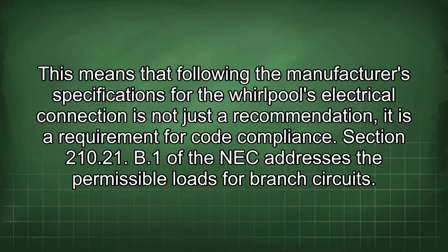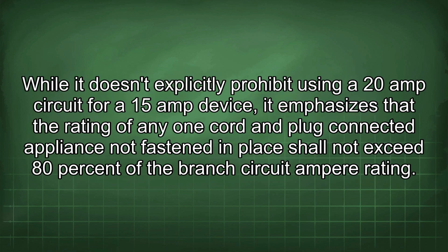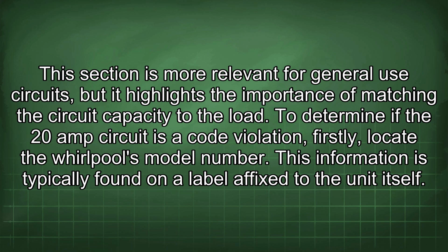Section 210.21(B)(1) of the NEC addresses the permissible loads for branch circuits. While it doesn't explicitly prohibit using a 20 amp circuit for a 15 amp device, it emphasizes that the rating of any one cord and plug connected appliance not fastened in place shall not exceed 80% of the branch circuit ampere rating. This section is more relevant for general use circuits, but it highlights the importance of matching the circuit capacity to the load.